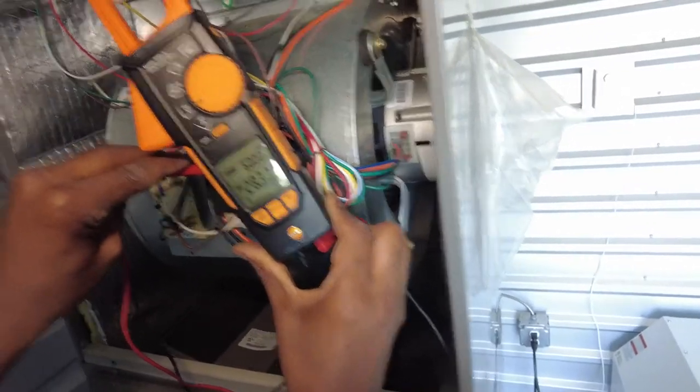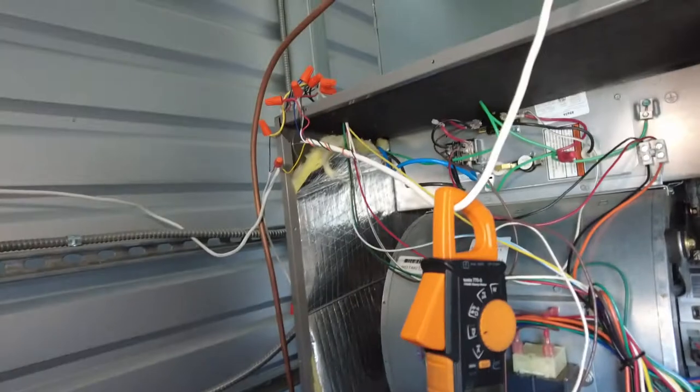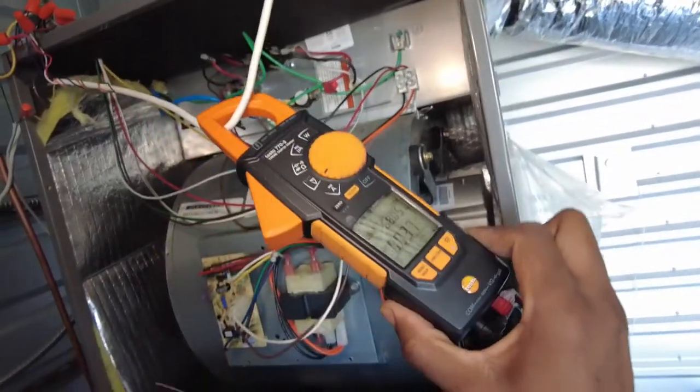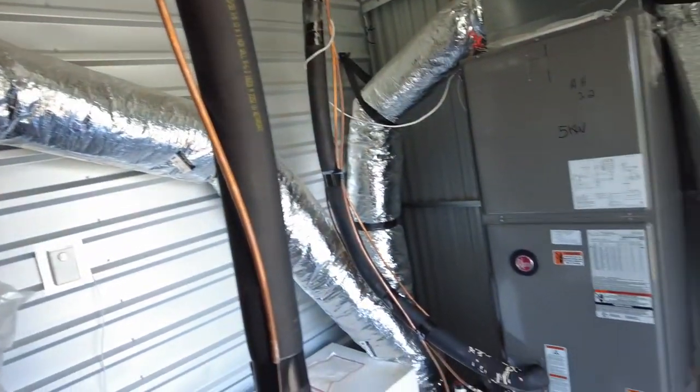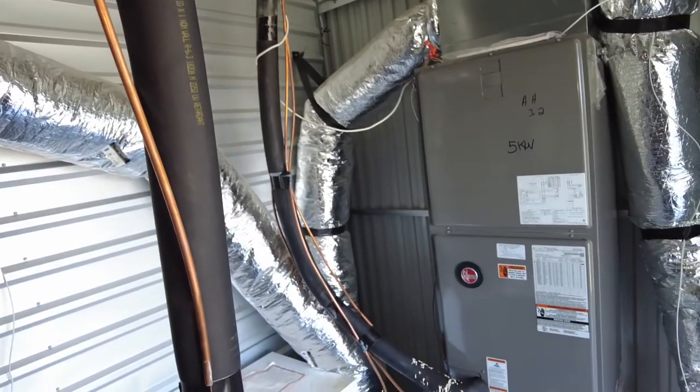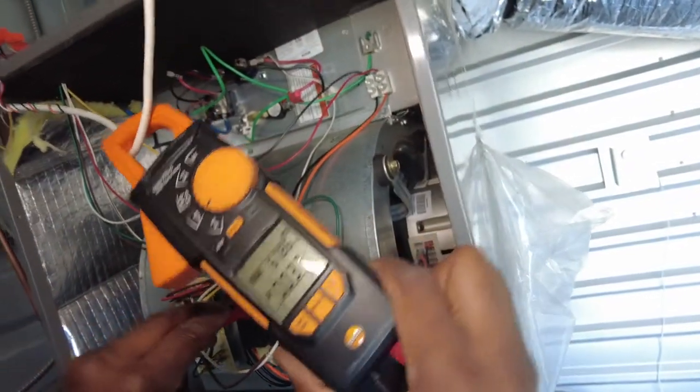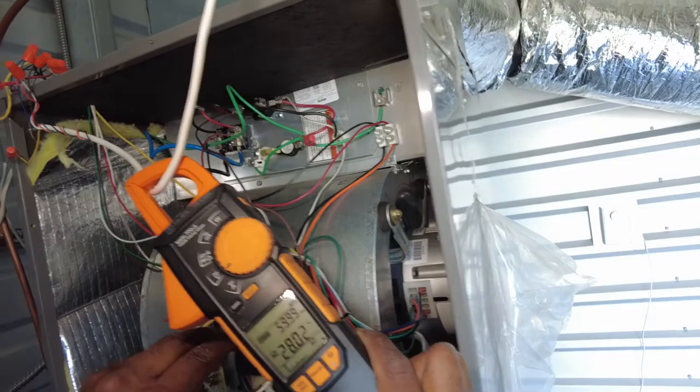There you go, 28 volts. Now we should have enough boost to pull that contactor in and keep it in. And like I said, I just checked that unit. That one's got 22 volts too going to the contactor. It's holding, but it needs to be swapped as well. So all the units probably in this whole facility are going to have to be changed over. 28 volts looks a whole lot more reasonable.